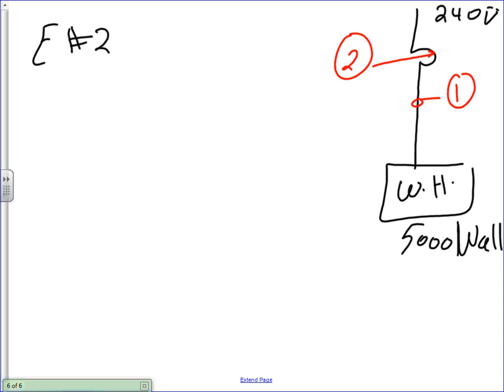Okay? And let's say it wasn't within sight, and I'm going to size a disconnect. That will be number 3. Number 3 is my disconnect, right? So if it's not within sight of the overcurrent protection device, I need to size a disconnect. That's it. What happened to the controller and the overload? That's all built into the water heater. Cool? Built into the water heater.